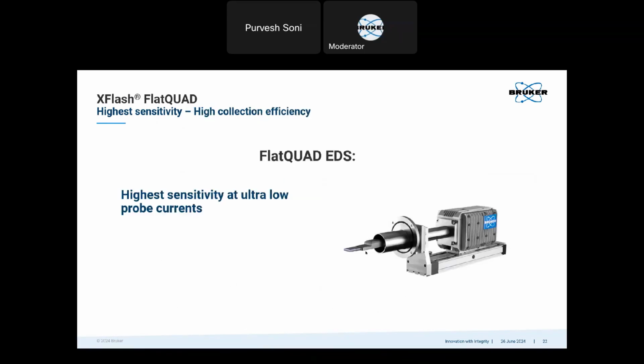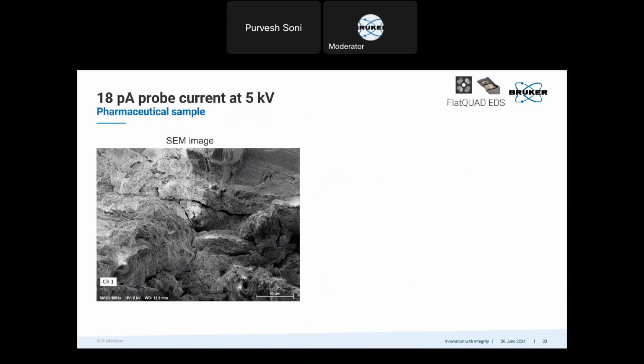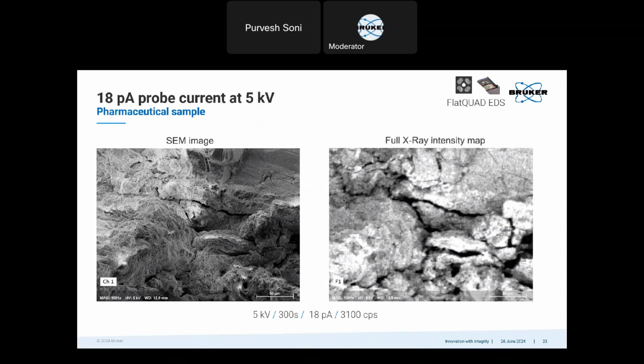So then let's see some ultra low probe current examples. This is a pharmaceutical tablet which was charging heavily, and because of this, I had to go to the lowest possible probe current on the microscope. It was 18 picoamperes at 5 kV. So this is what I got. So this is at 5 kV, 18 picoamperes. I got high count rate of 3,100 counts per second, which is very good considering the very gentle probe conditions.